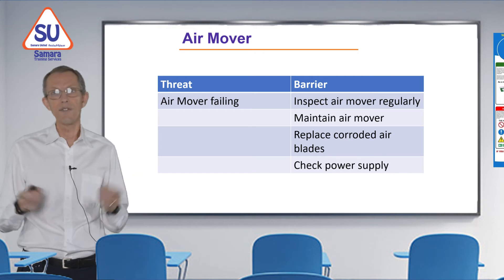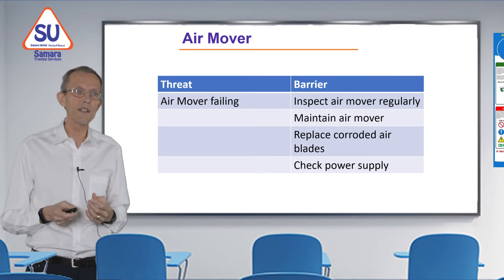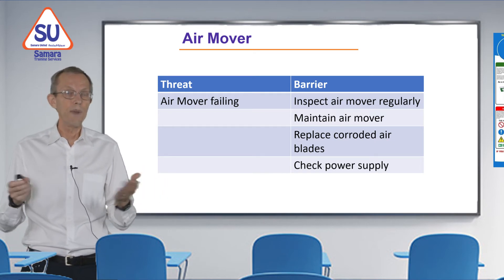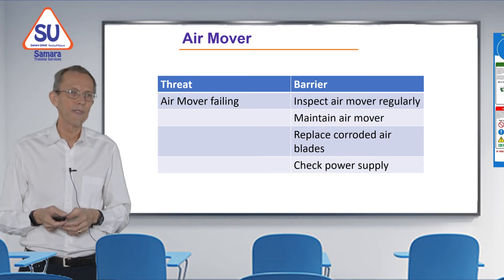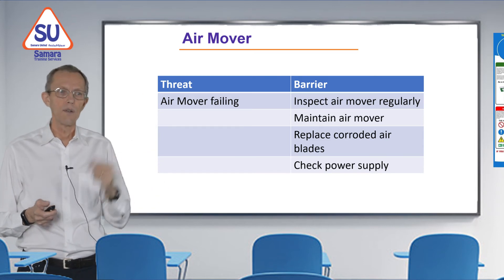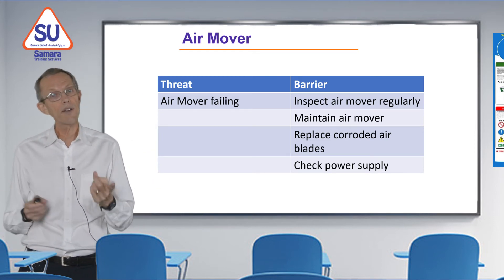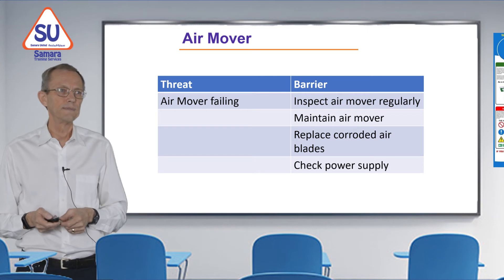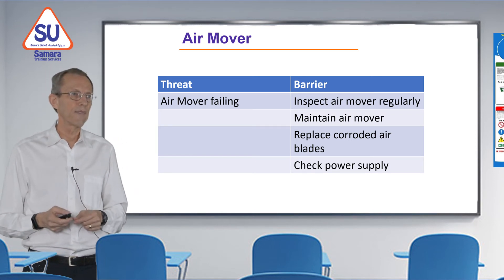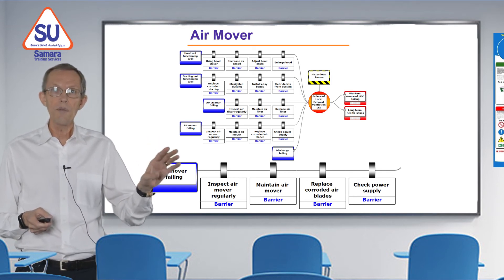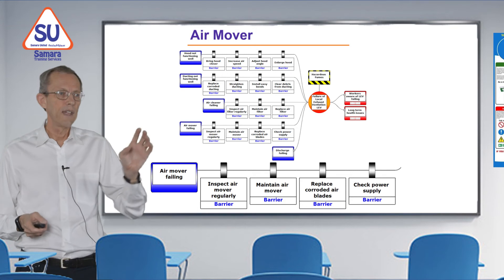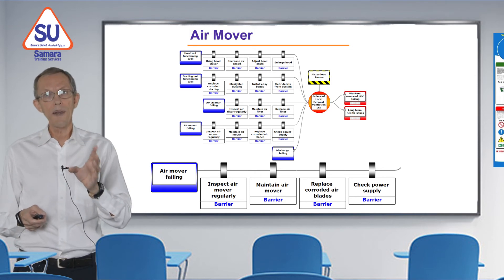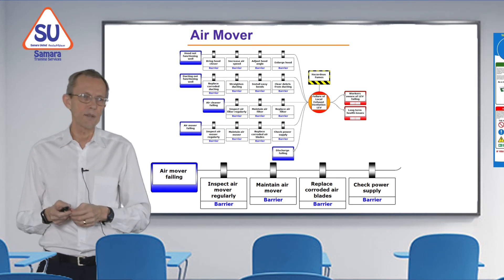The air mover — the fan — is failing. Again, we could inspect it regularly to check it's working as it should. We could maintain it, as all machines benefit from regular maintenance. If the blades are corroded, we could replace them. And we can check the power supply — if power is down, the blades will turn slowly and not work well. On the diagram, the fourth threat line shows: air mover failing, with four barriers — inspect the fan, maintain it, replace corroded blades, and check the power supply.